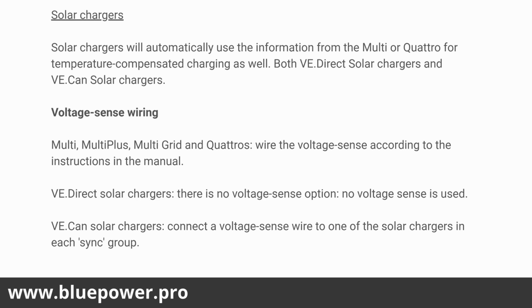Okay, that's on the MPPT. So the solar chargers will automatically use the information of the Multi or Quattro temperature-compensated charging, as well as the VE.Direct chargers. So if you've got the GX device connected, your MPPTs or the other charging sources will automatically also adapt to the temperature compensation settings for your lead-acid battery bank. Okay, that's just for lead-acid usage.